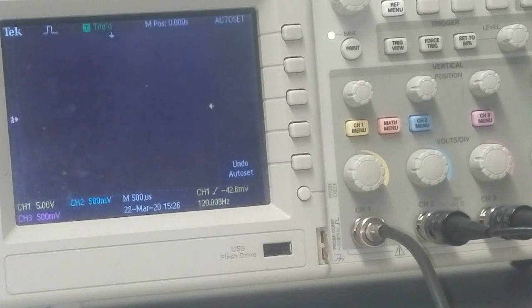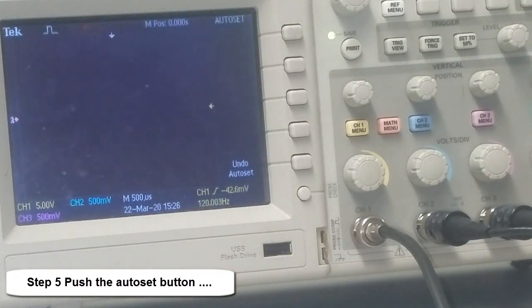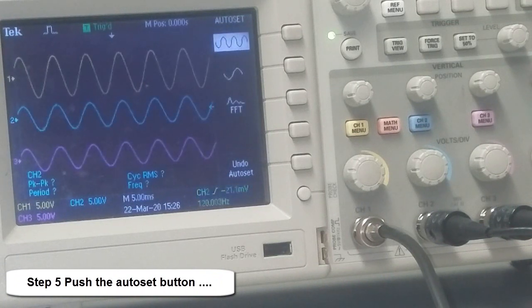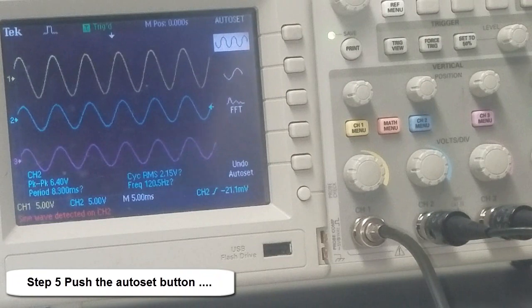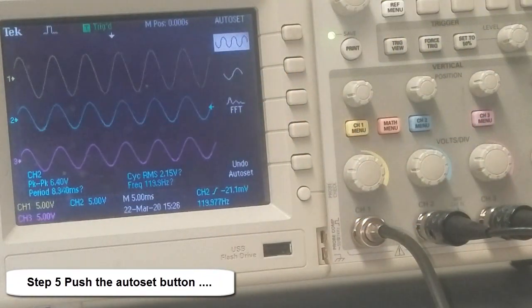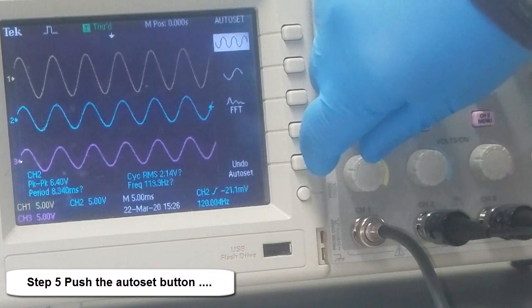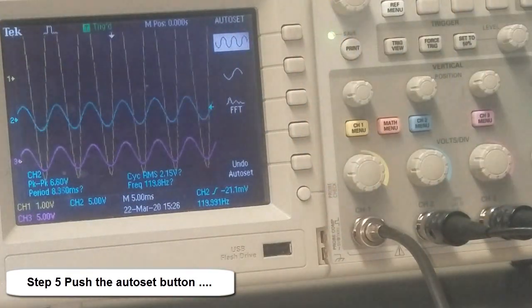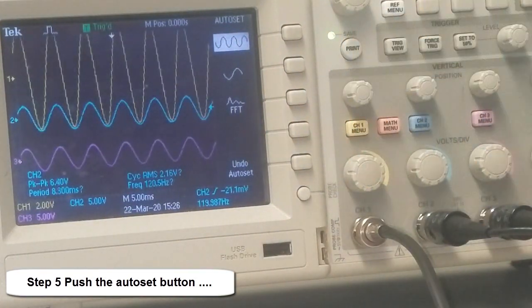Now I'm going to do auto set, and let's see what we have when we do the auto set. You're going to see 3 signals on the screen. Now when you want to measure signals, you don't want to leave it at the auto set. The auto set will show you the shape of the signal, but you really want to measure the signals. So you need to zoom in to get more accurate readings. So I'm going to zoom in with this one. I make it bigger, which is channel 1.